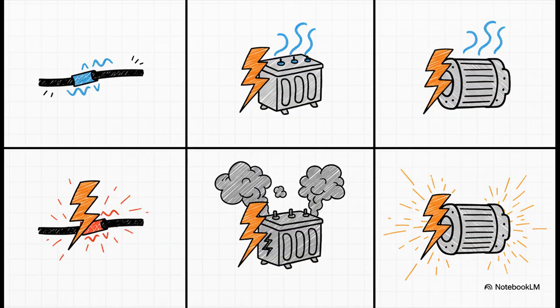Think about it. Every single cable, every transformer, every generator out there has a physical limit. It can only handle a specific amount of overcurrent for a specific amount of time before it suffers permanent, catastrophic damage. And that limit is what we call its damage curve.